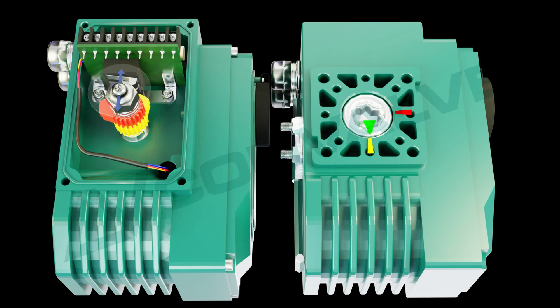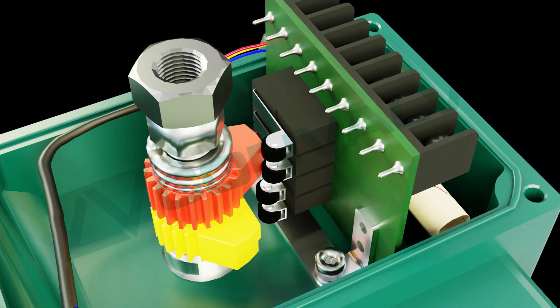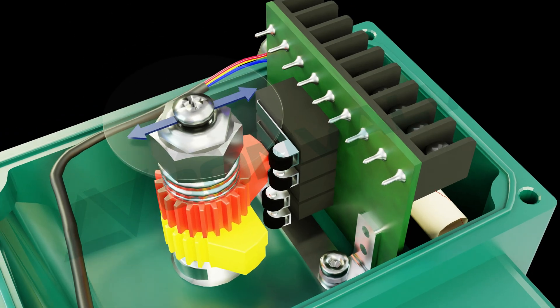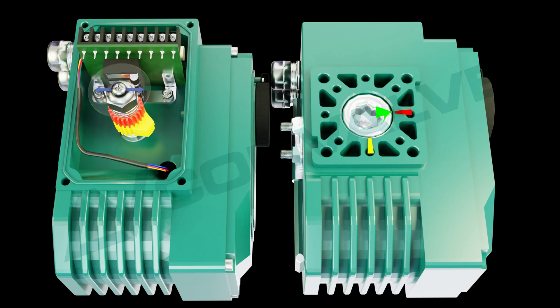Setting the full closed position: manually operate the actuator to the fully closed position. Use a lever to loosen the nuts on the limit cam, rotate the limit cam until the red closed limit switch is activated. Ensure that the actuator's connection to the valve is properly aligned and securely positioned. Once everything is correctly aligned, securely tighten the cam nut.